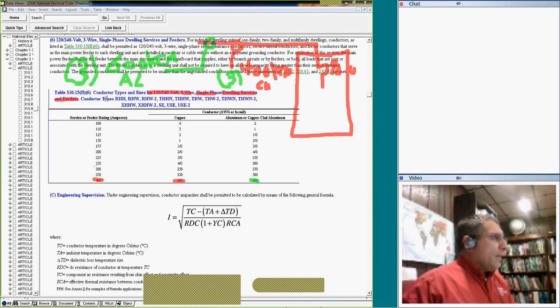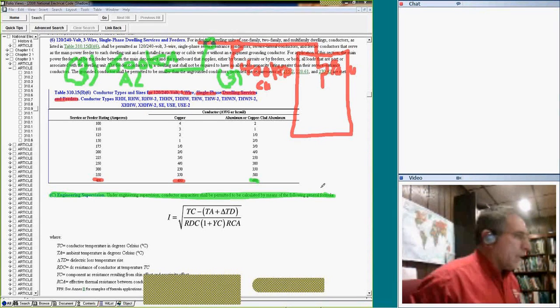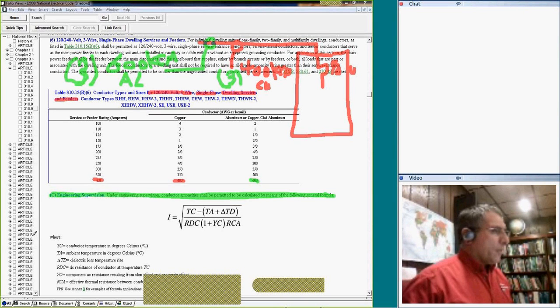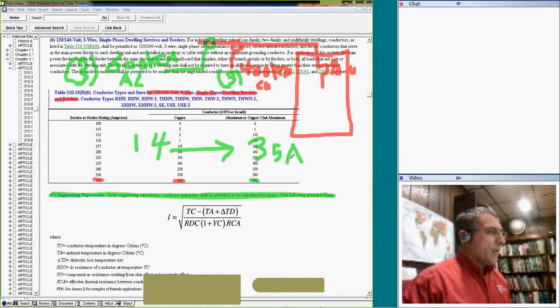If you don't care, under engineering supervision, you have to have engineering supervision. Under engineering supervision, conductors shall be permitted to be calculated by means of the following formula. So I, as a registered engineer, decided to go with that 400 kcm. I want to use my engineering formula to come up with different numbers. Can I do that? Absolutely. Under engineering supervision, my friends, I can make number 14 carry 35 amps, I'm exaggerating here, if my calculation proves it's not going to heat up based on this formula.